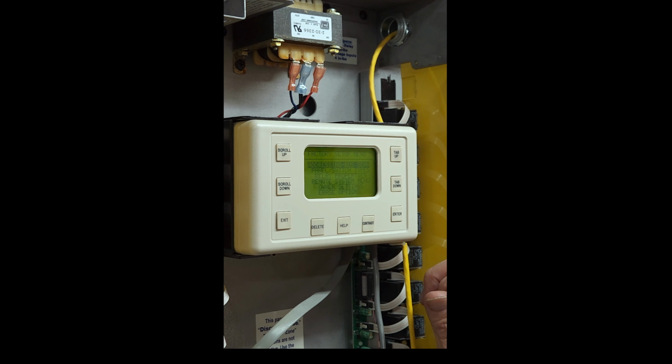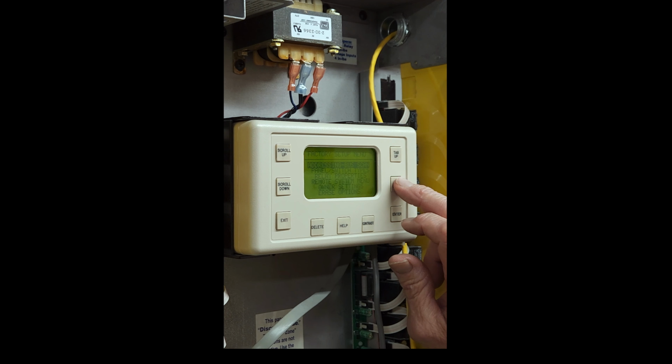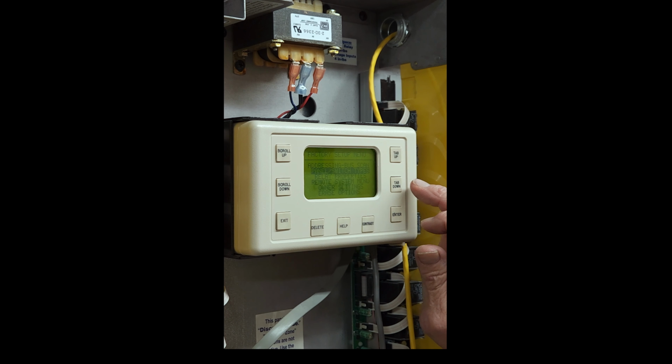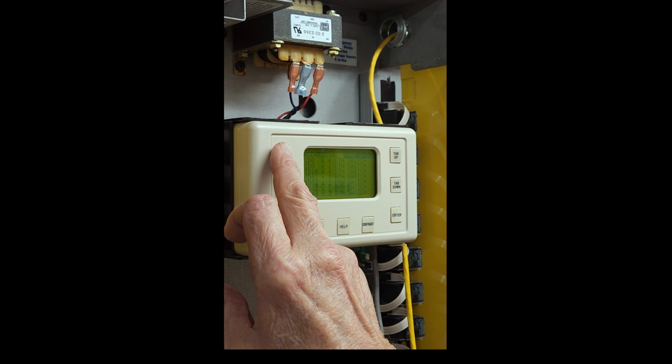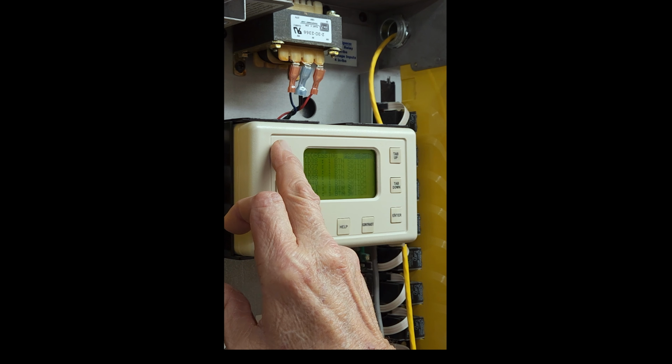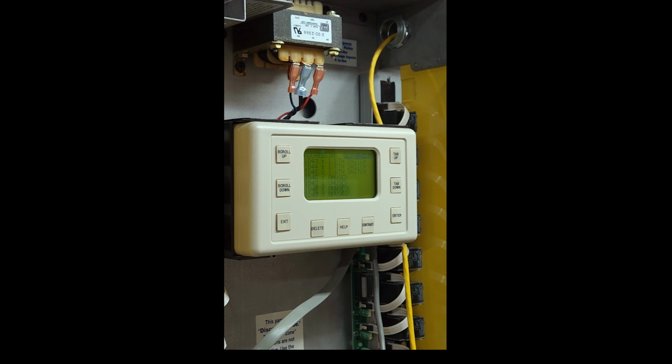Okay, hit enter. Tab down to panel switch type, because we want to give this switch a brand new number too. Forget about all the existing ones. Hit enter. Enter. Push scroll up until you see a number that says unused. Keep going. Scroll up, scroll up, scroll up. The first number you see that says unused. There it is, 46. Okay. We give it that, 46. So tab down to 46.